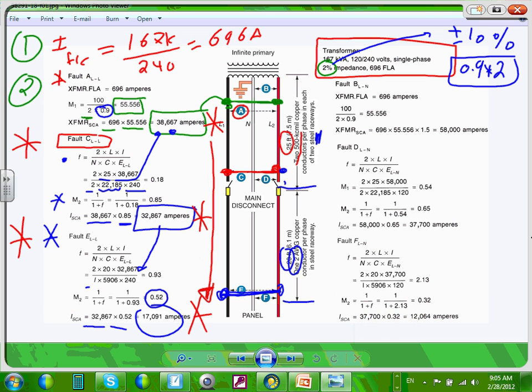On this side, we did the same calculation for line to ground. Can you guys see line to ground? Because on a single phase system or 3-phase system, guys, you can have line to line, or you can have line to ground. The line to ground will be a different value than line to line. Okay, if it's line to neutral or line to ground, can you guys see that? The same thing, you take the same amp, divided by the same multiplier, get you the same multiplier, exactly like the 3-phase. Can you guys see that?